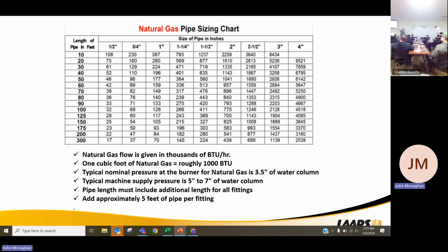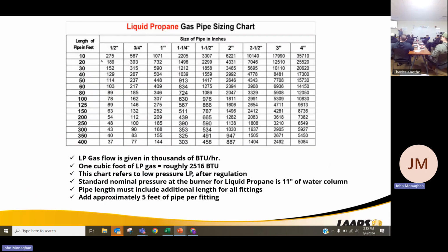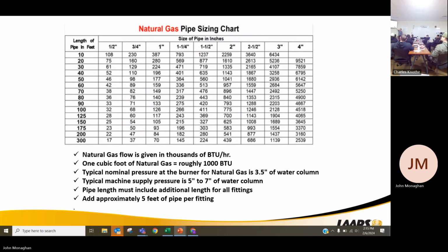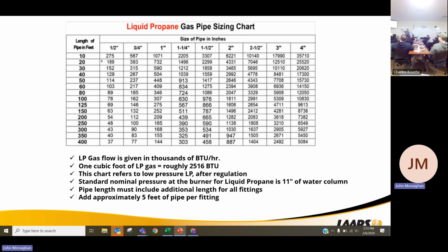But we have a 50,000 BTU boiler. Go back to that chart. I can run 10 feet of half-inch pipe. Will deliver me 108,000 BTUs. 20 feet of half-inch pipe will be 75,000 BTUs. So I can run 20 feet of half-inch pipe to supply a 50,000 BTU unit. Same chart as for LP. LP changes a little bit. LP is usually running at higher pressures.